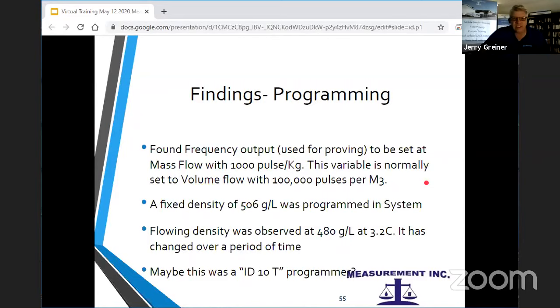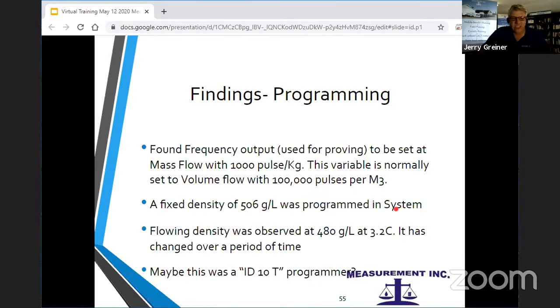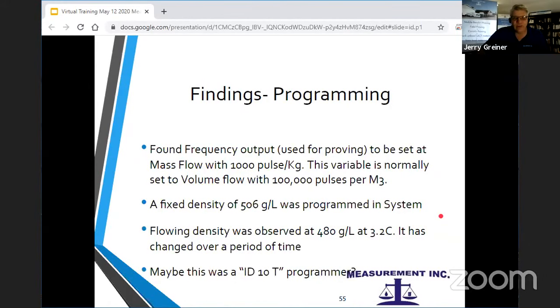The density was fixed in their system at 506 grams per liter, which is what it was when it was originally programmed, and in year 1, that was their density. The flowing density changed over time as their process changed, and really as it got better, they were able to get more and more liquids out of the gas stream, and their density went down to 480. And so that change from 506 to 480 is basically the exact same change we saw in the difference in the meter factor. Sometimes we call this an ID10T programmer. It was really confusing the way that it was used in this.